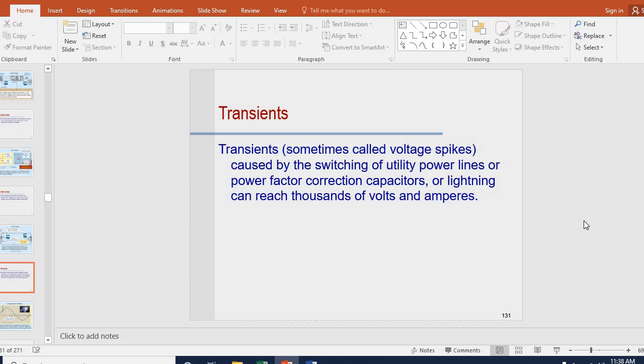Transient, sometimes called voltage spikes, caused by the switching of utility power lines or power factor correction capacitors, or lightning, can reach thousands of volts and amperes. Happens a lot. There's some of that corrective capacitance. If you have a power factor corrector bank, it sees the voltage and it sees it needs more capacitance. It throws in starters to add more capacitance to the line, and sometimes it can spike the voltage.